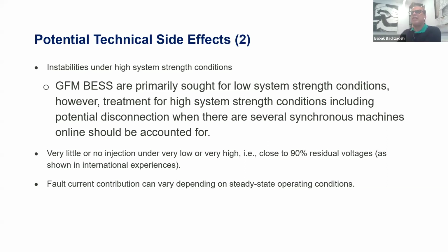So with grid forming inverters, essentially they most like a system that is weak in our common understanding, but maybe there is a classification of what weakness is, and we have voltage weakness and current weakness. Up to this point, we have only been talking about voltage weakness, and that works very well for grid following inverters and also synchronous machines. The stronger the voltage source is, the better it will be, and the current control is essentially default. That's the very notion of having grid following inverters, whereas with grid forming inverters it is the other way around.